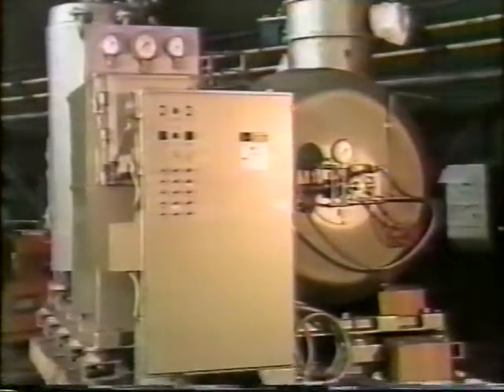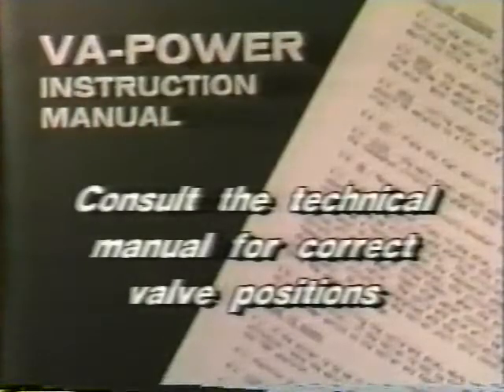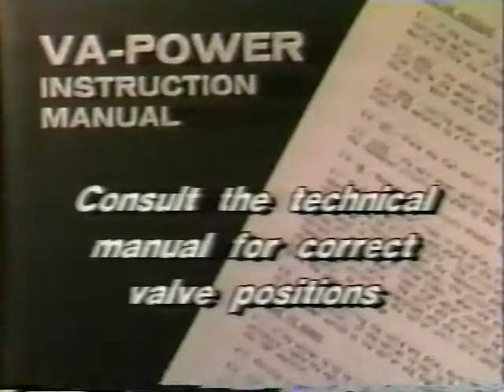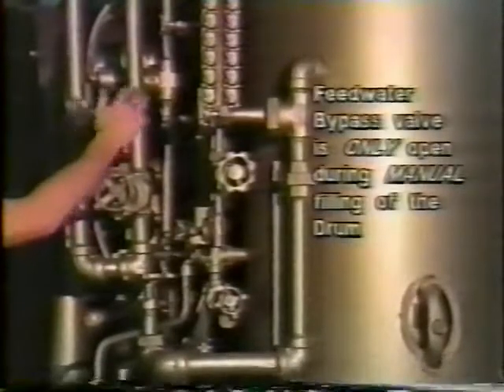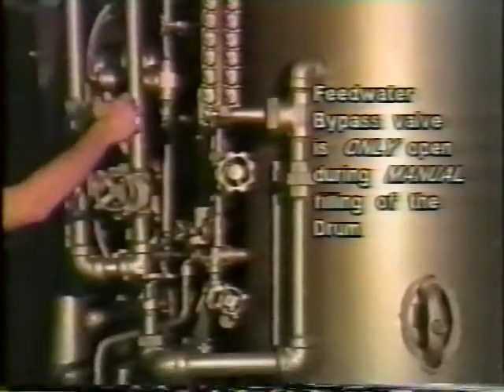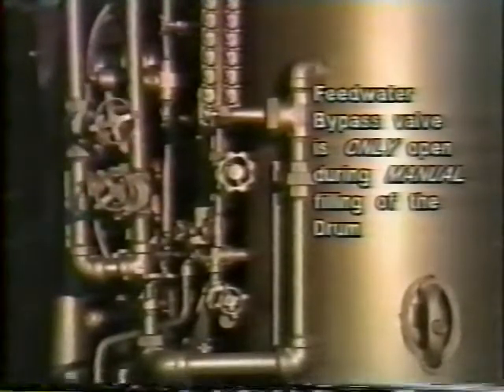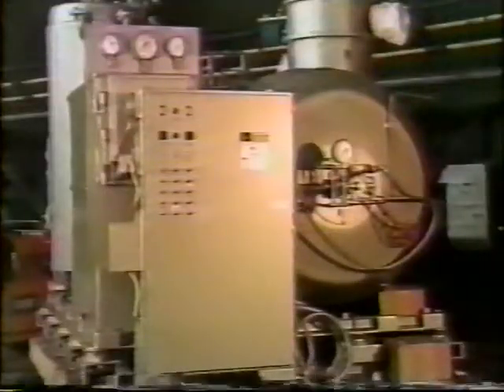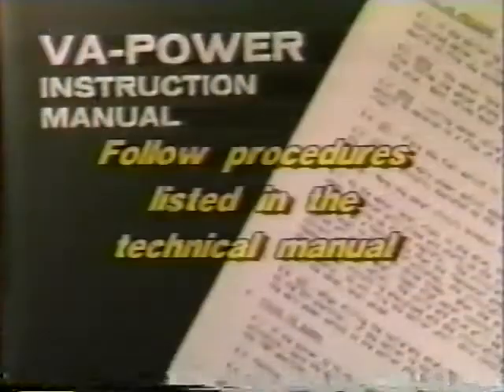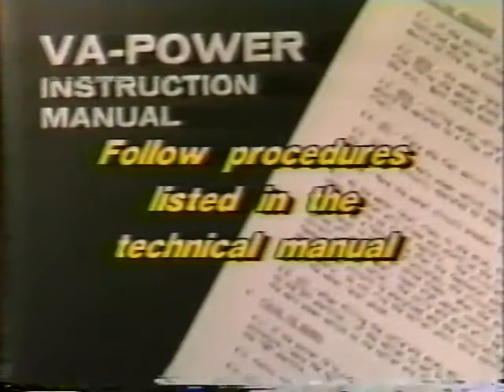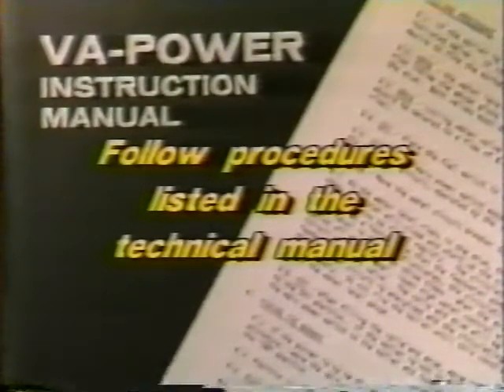During normal boiler operations, position the valves as directed in the operating instructions contained within the technical manual. Also, keep in mind that the feed water bypass valve to the boiler is only open during manual filling of the drum. If the boiler needs to be filled, follow the filling procedures listed in the technical manual. Once the boiler is filled, it's ready to be fired.